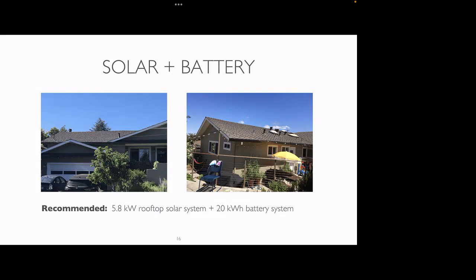Here we're trying to max out their roof space and what can fit on a 100 amp panel, sort of the maximum solar roof system that can fit on 100 amp panels, so a 5.8 kW system. And then we were specifying a 20 kilowatt hour battery system, although a 10 kilowatt hour battery system would work just fine as well.